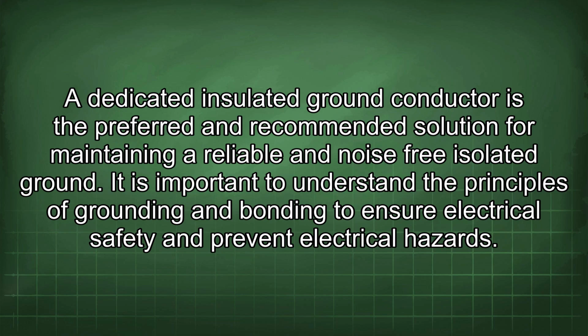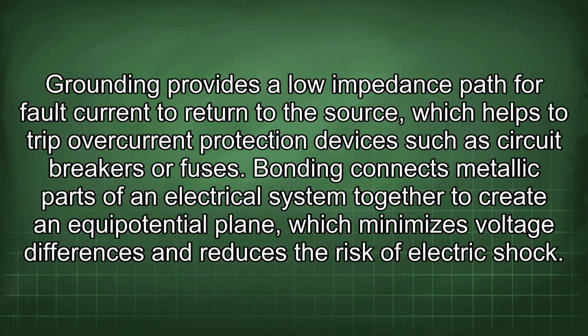It is important to understand the principles of grounding and bonding to ensure electrical safety and prevent electrical hazards. Grounding provides a low impedance path for fault current to return to the source, which helps to trip overcurrent protection devices such as circuit breakers or fuses. Bonding connects metallic parts of an electrical system together to create an equipotential plane, which minimizes voltage differences and reduces the risk of electric shock.